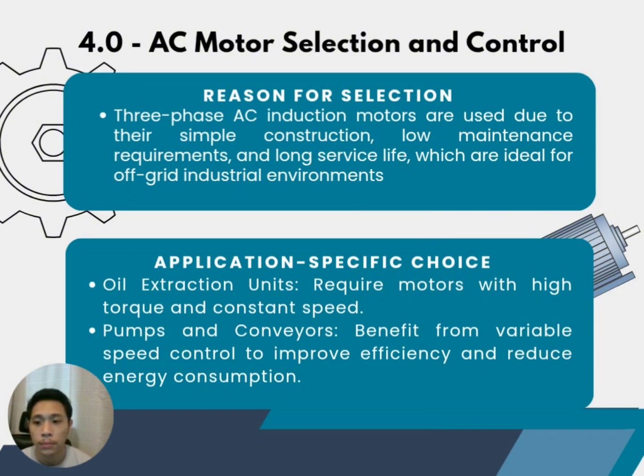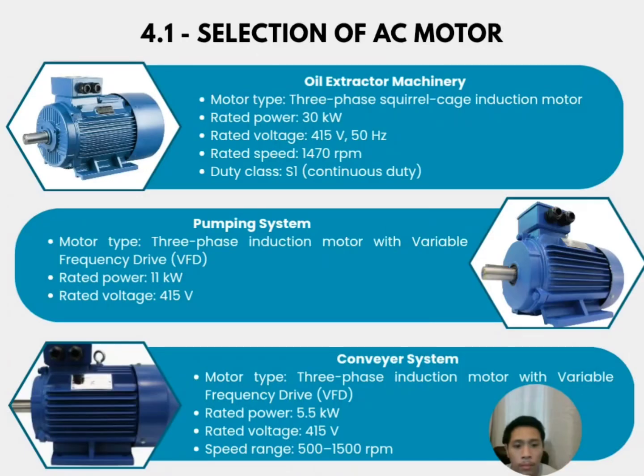The second one is for pumps and conveyors. We focus on efficiency, and these machines don't always need to run at full speed. By using variable speed control, we can slow them down when they are not busy. This saves a lot of electricity and makes our system much more efficient. Moving on to the next part, which is the selection of AC motor.